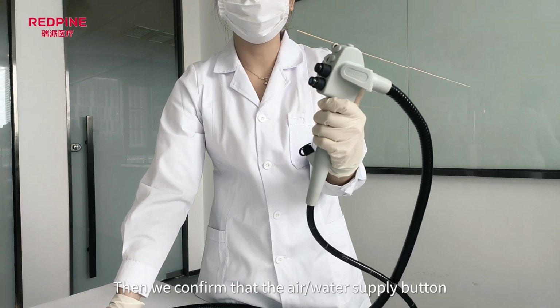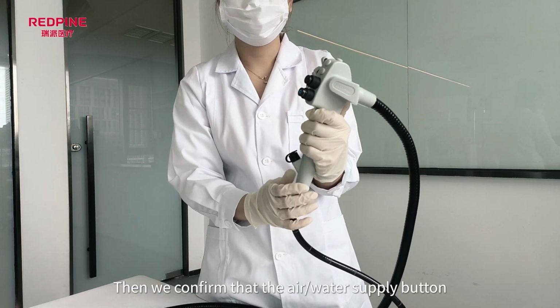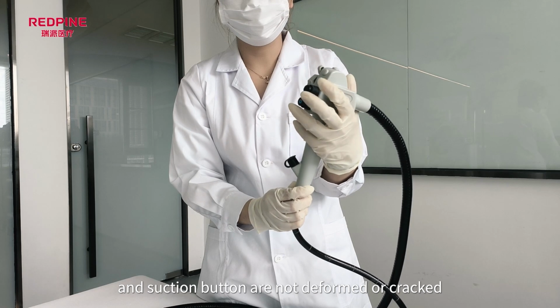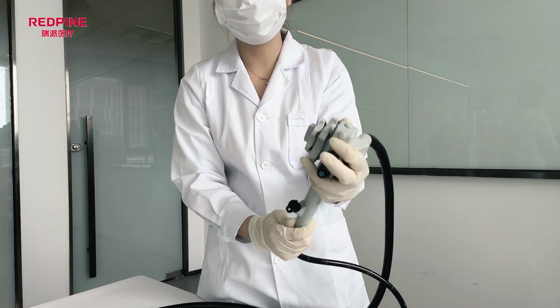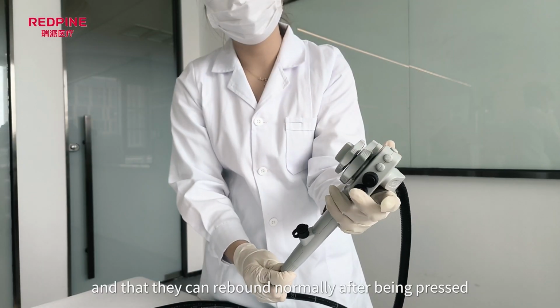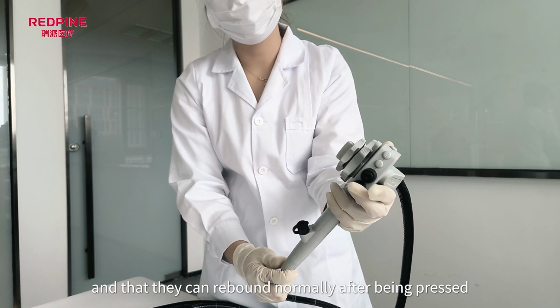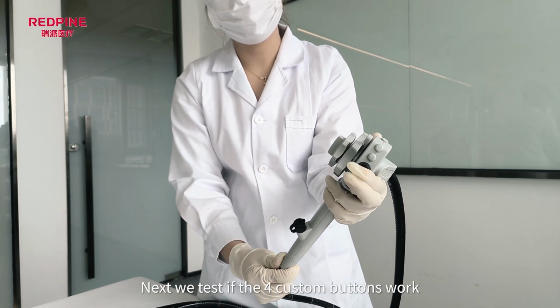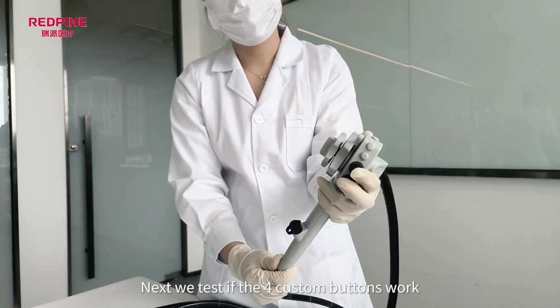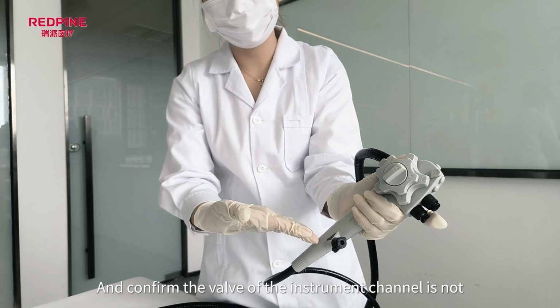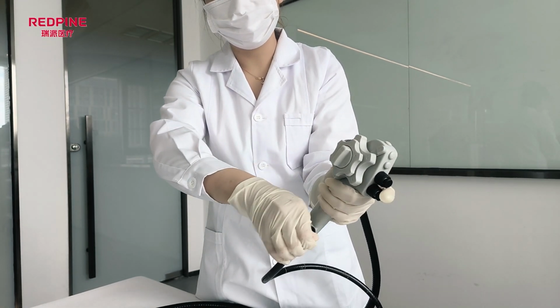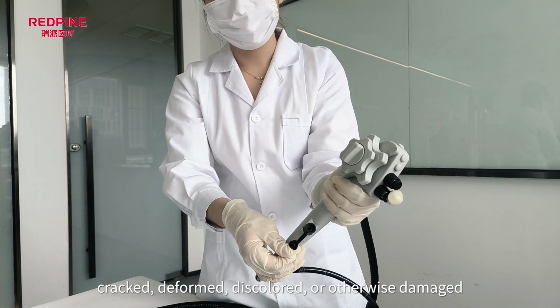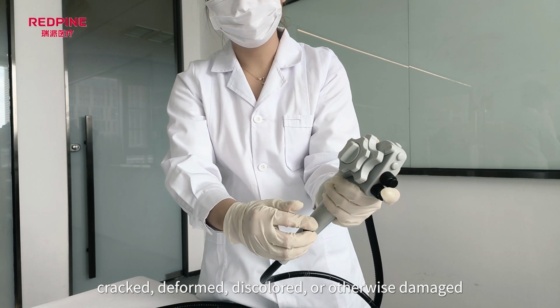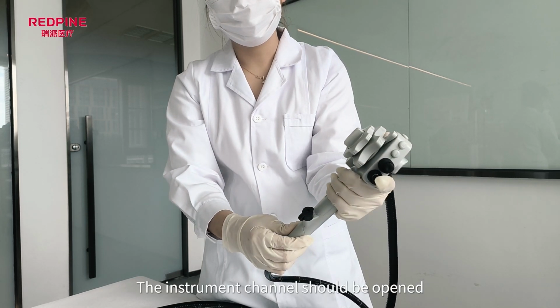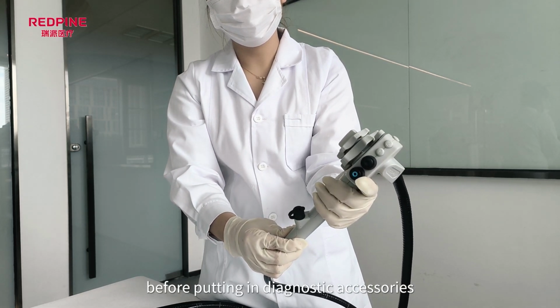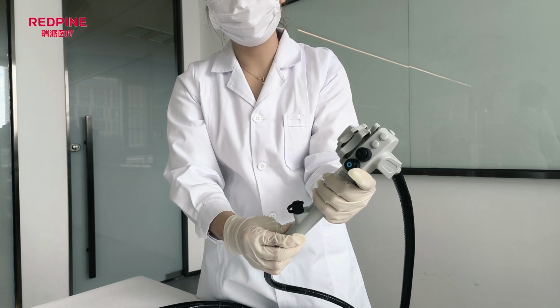Then we confirm that the air or water supply button and suction button are not deformed or cracked, and that they can rebound normally after being pressed. Next we test if the 4 custom buttons work, and confirm the valve of the instrument channel is not cracked, deformed, discolored or otherwise damaged. The instrument channel should be opened before putting in diagnostic accessories.